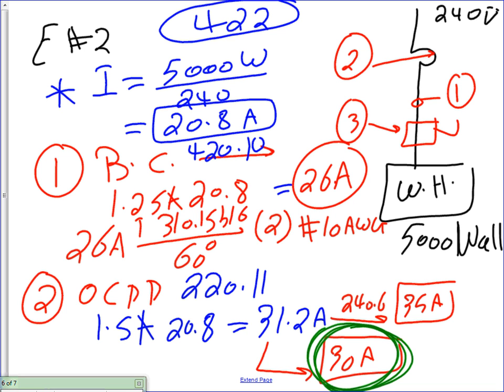You can't go up on a circuit breaker. You can always go down. I use 30 amps, and I keep my conductors number 10, and that's what we did, what you guys sized, right? Number 10, that's what we came up with, number 10, 30 amps. Can you give a thumbs up, Chad? We understand fully that we can go up and we went down because we don't want to pull a larger conductor. That's why we become designers, guys, and we start thinking about things, not just implementing them. Okay, so that's basically it, so you have a 30 amp. You have your 30 amp water heaters.